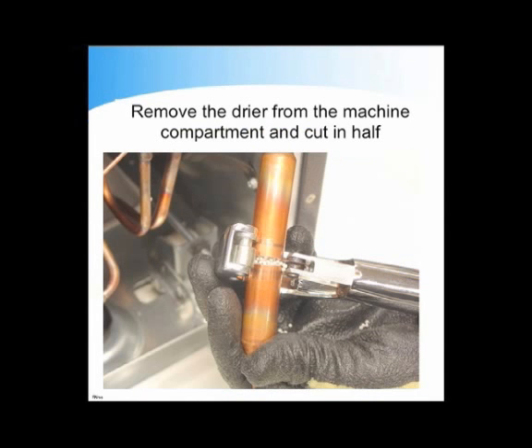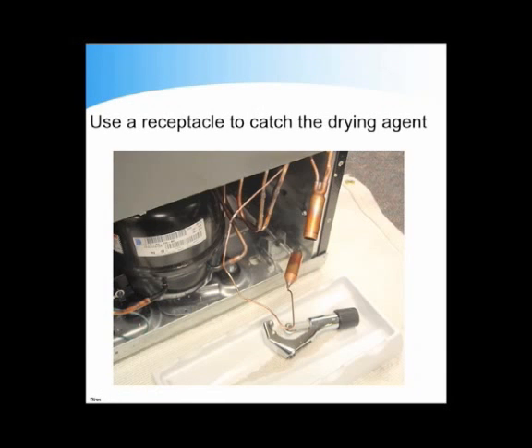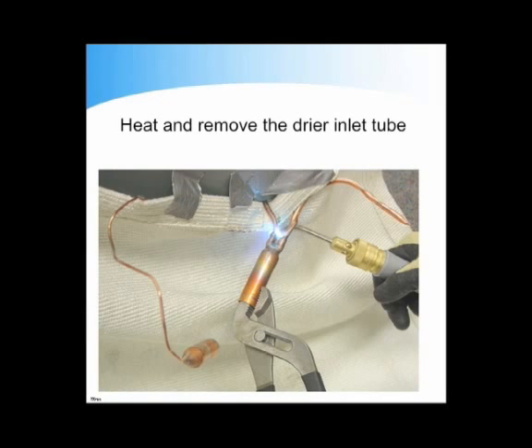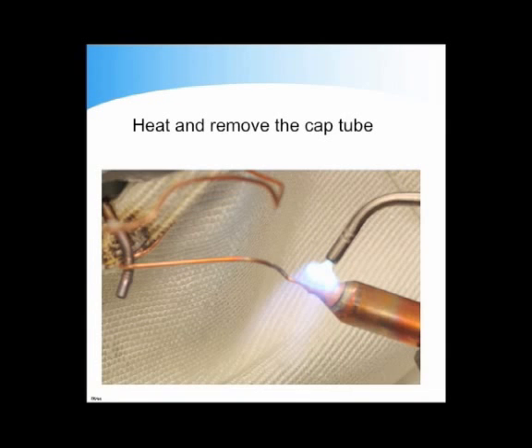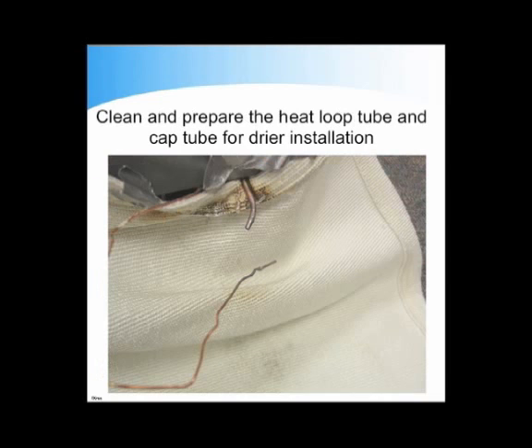Remove the dryer from the machine compartment and cut in half. Use a receptacle to catch the drying agent. Heat and remove the dryer inlet tube. Heat and remove the cap tube. Clean and prepare the heat loop tube and cap tube for dryer installation.